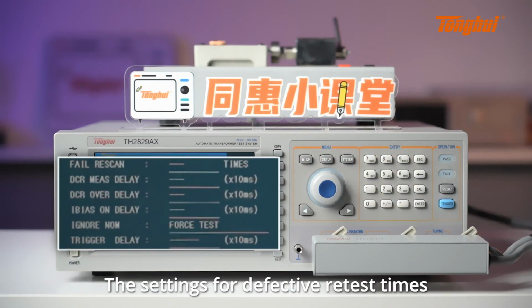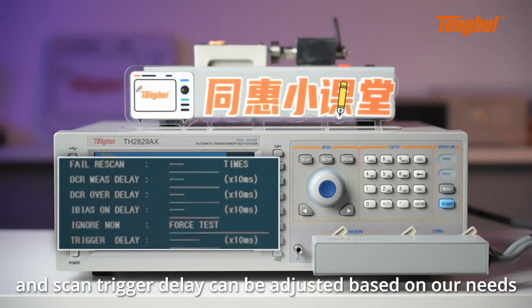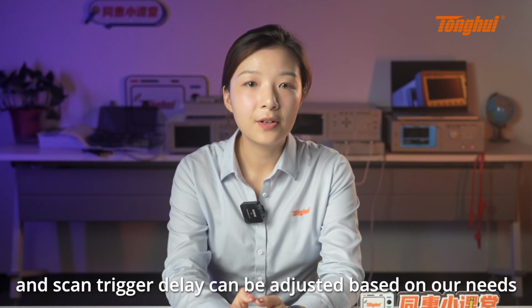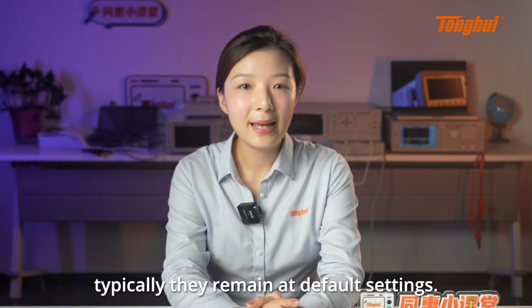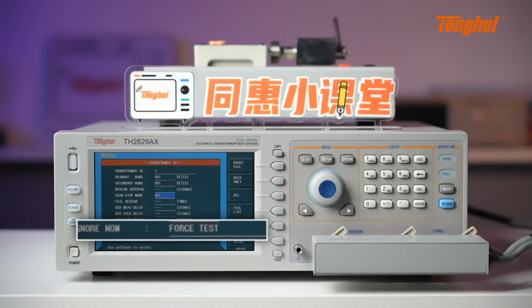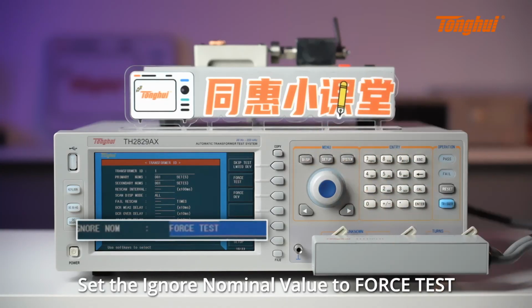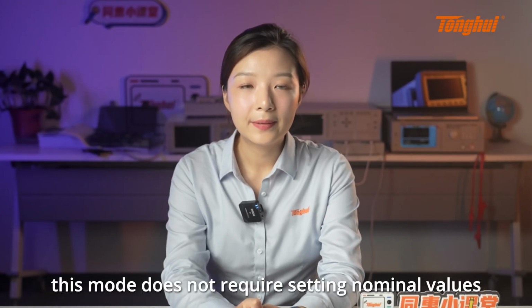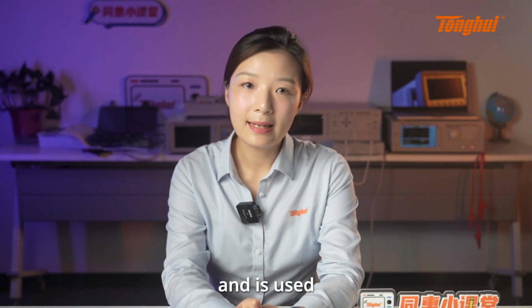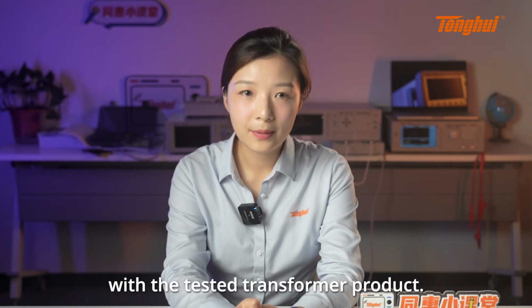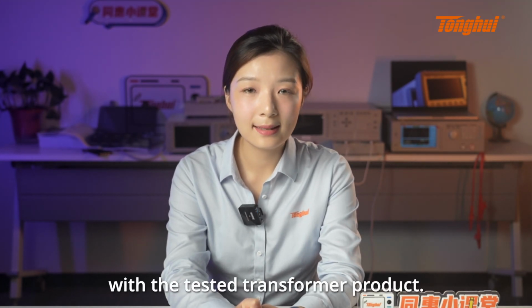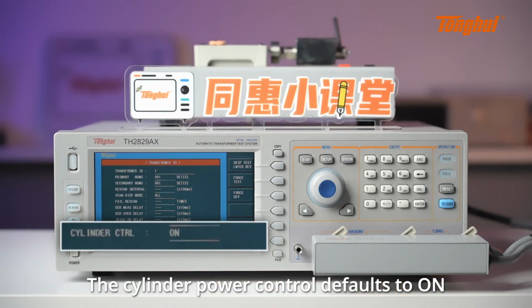The settings for defective retest times, DCR test delay, DCR result delay, bias current test delay, and scan trigger delay can be adjusted based on your needs. Typically, they remain at default settings. Set the ignore nominal value to force test. This mode does not require setting nominal values and is used when we are not familiar with the tested transformer product. The cylinder power control defaults to on.